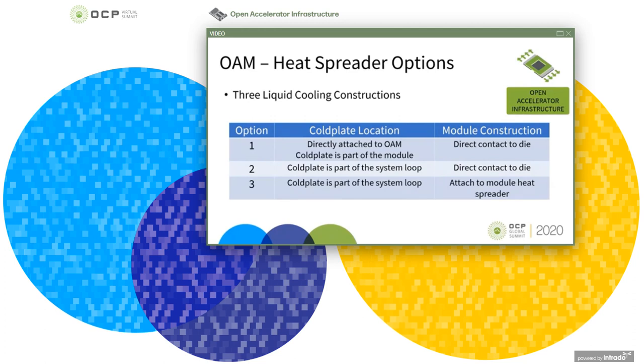However, this requires that the liquid cooling loop cannot be tested until the OAMs, with their attached cold plates, are installed into the loop. This requires additional care when testing the liquid cooling loop and creates additional risk when replacing OAMs in the field.